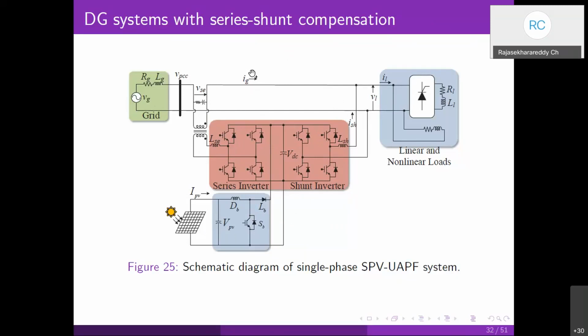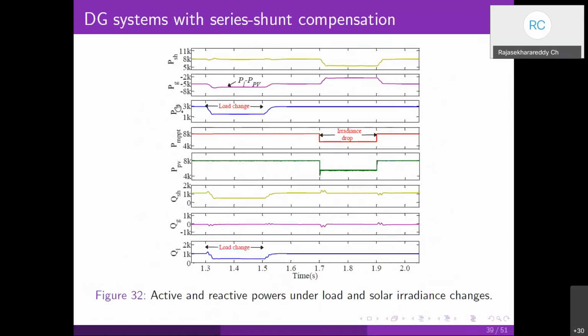If this is reversed, the opposite thing will happen. If the grid current direction is reversed, that means the grid current and grid voltage are out of phase. In case of a voltage sag, the series converter then absorbs the power and feeds it back to the grid through the shunt converter. Those things we can see here. The thing you need to observe is that the grid is always free from reactive power generation, whereas the shunt converter reactive power varies based on your load variation, and the shunt converter active power variation is decided by the sag and swell periods.